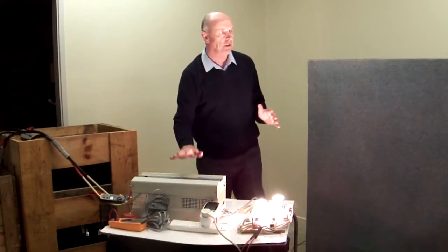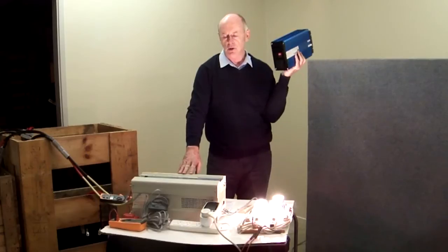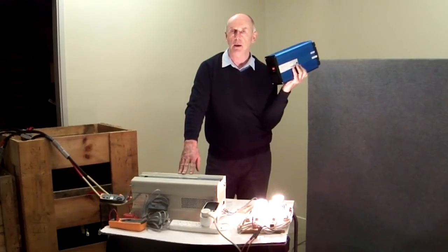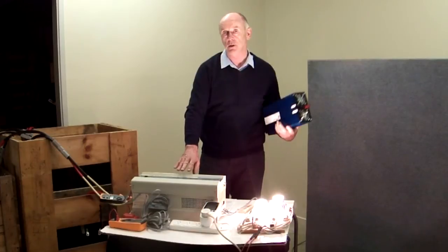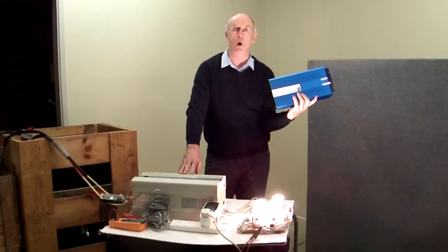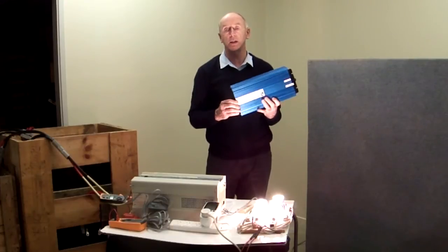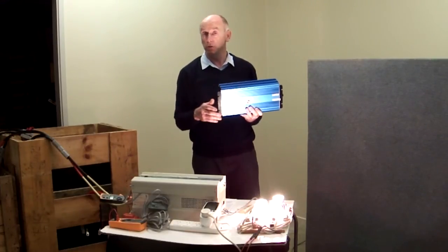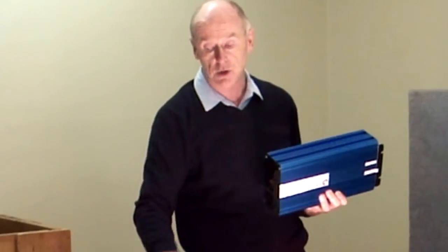One of the big advantages of this type of inverter compared to the high frequency inverter is the amount of surge power it can handle. This will handle 3 times rated power — in this case a 2000 watt inverter, 12 volt in, 240 volt out — so it'll handle 6000 watts for 20 seconds or more. The high frequency inverter will only handle approximately 2 times rated current, so that would only handle 4000 watts for maybe 0.2 of a second. 0.2 of a second compared to 20 seconds, and only 2 times rated power as against 3 times rated power.